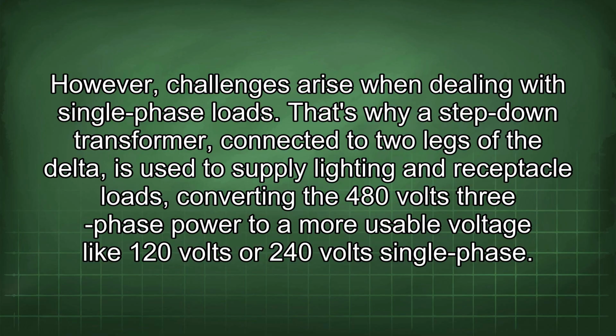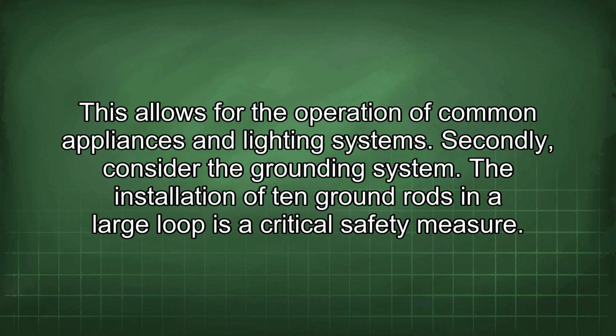However, challenges arise when dealing with single-phase loads. That's why a step-down transformer, connected to two legs of the delta, is used to supply lighting and receptacle loads, converting the 480 volts three-phase power to a more usable voltage like 120 volts or 240 volts single-phase. This allows for the operation of common appliances and lighting systems.